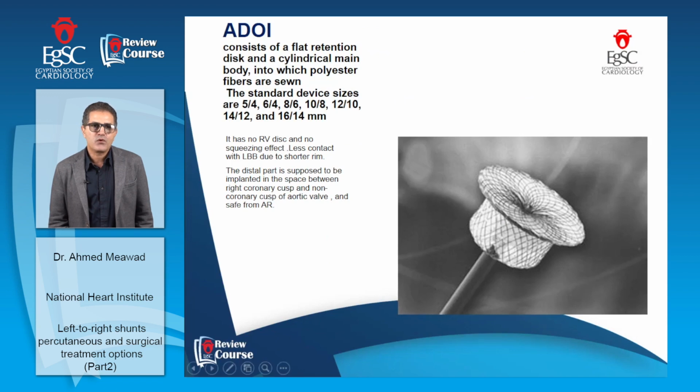The duct occluder 1 consists of a flat retention disc and a cylindrical body. There is no left atrial disc or right side disc. So it doesn't cause a squeezing effect, and it doesn't cause heart block, except in rare cases in perimembranous VSD cases.